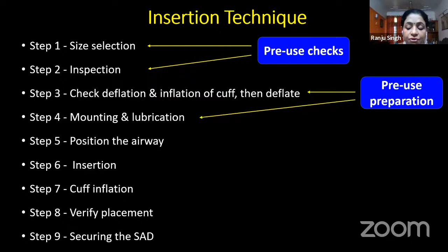So the first important step when you are given the device and asked to talk about it is the size selection. The correct size for each patient is a weight-based selection as per the manufacturer's guideline. It's okay if you don't remember which weight is associated with which size, because most of these devices have written on them which weight category they are meant for. As you can see in this picture, this is a number 3 ProSeal, which is recommended for patients weighing between 30 to 50 kgs.